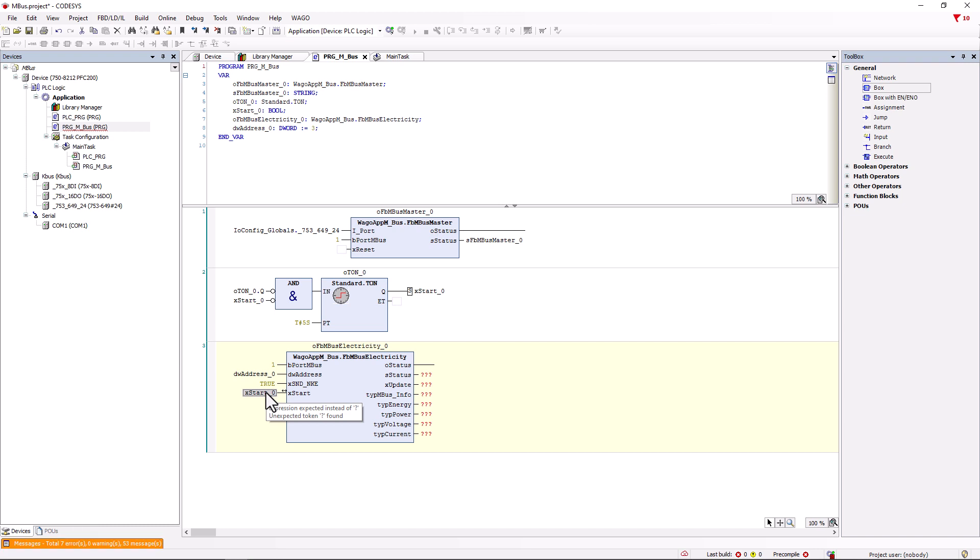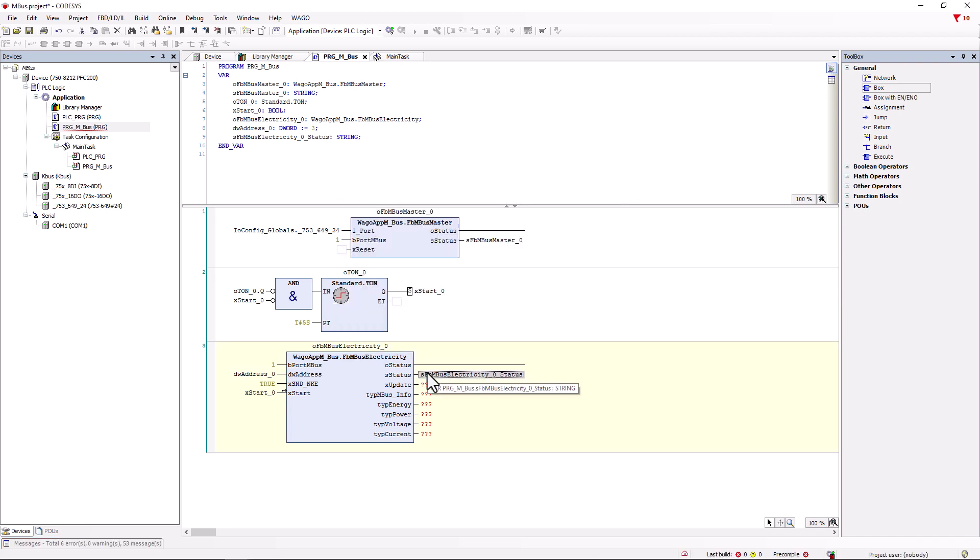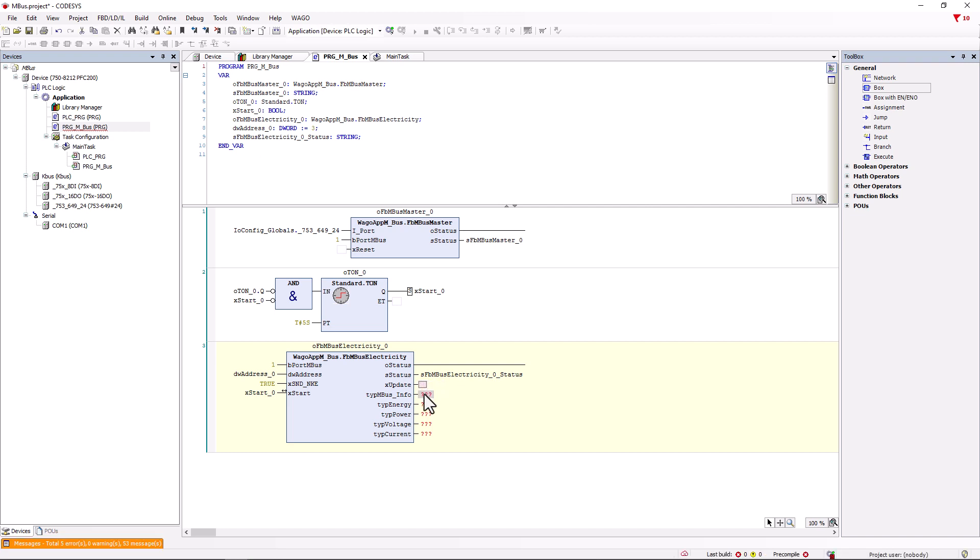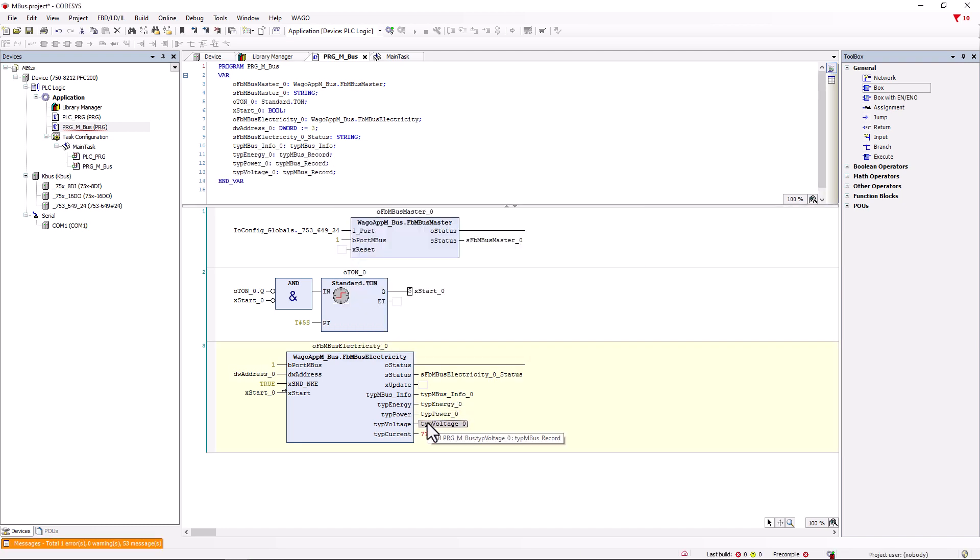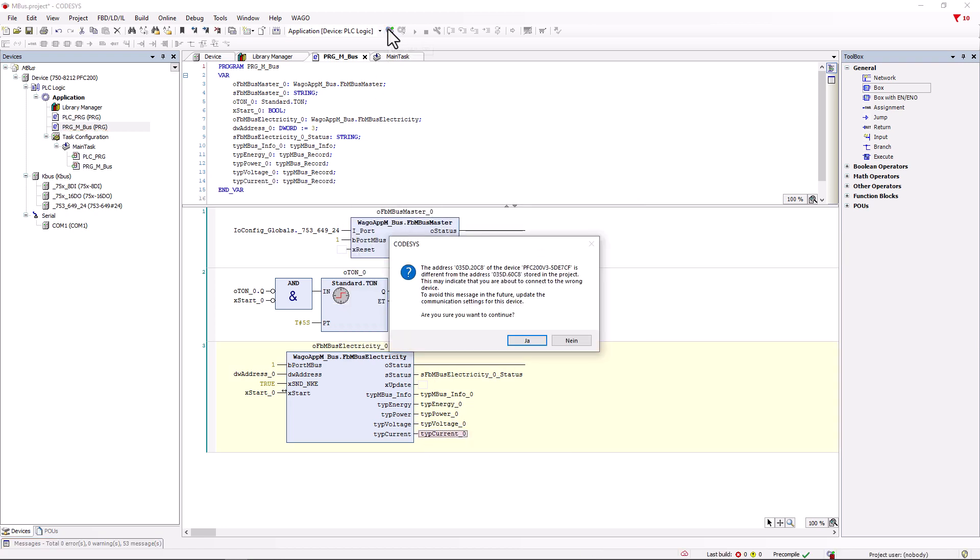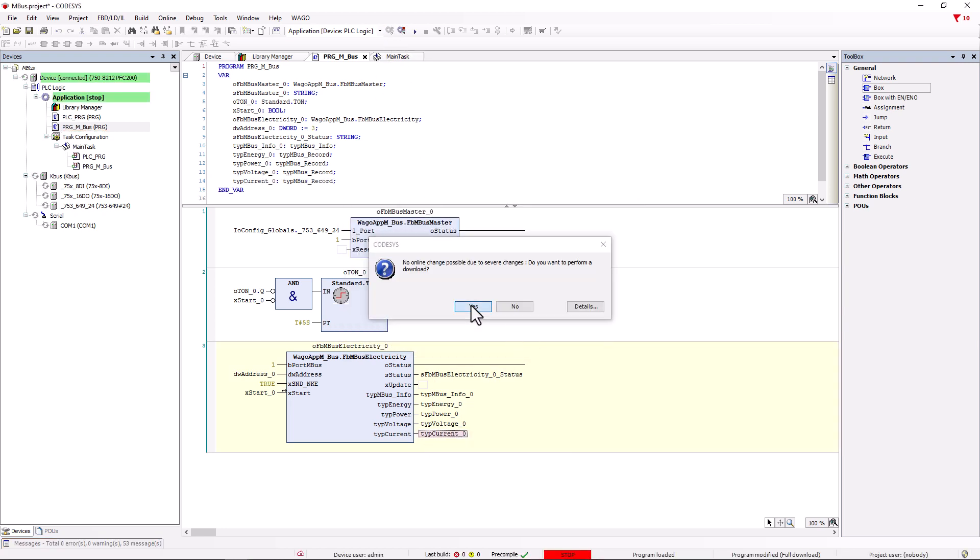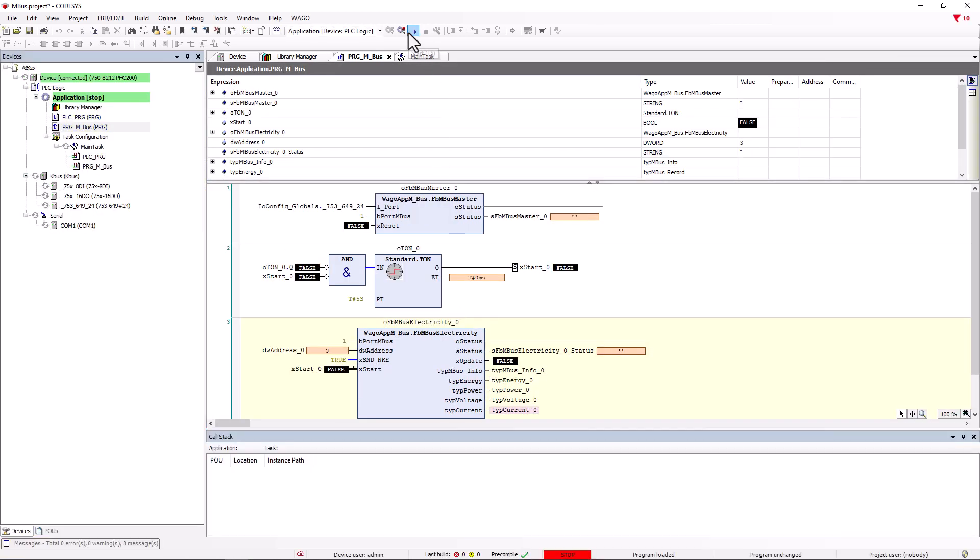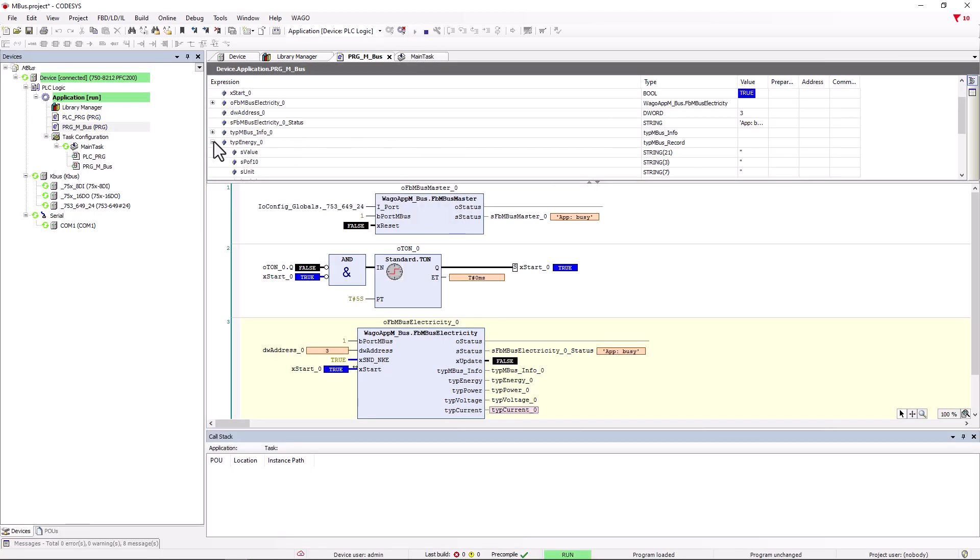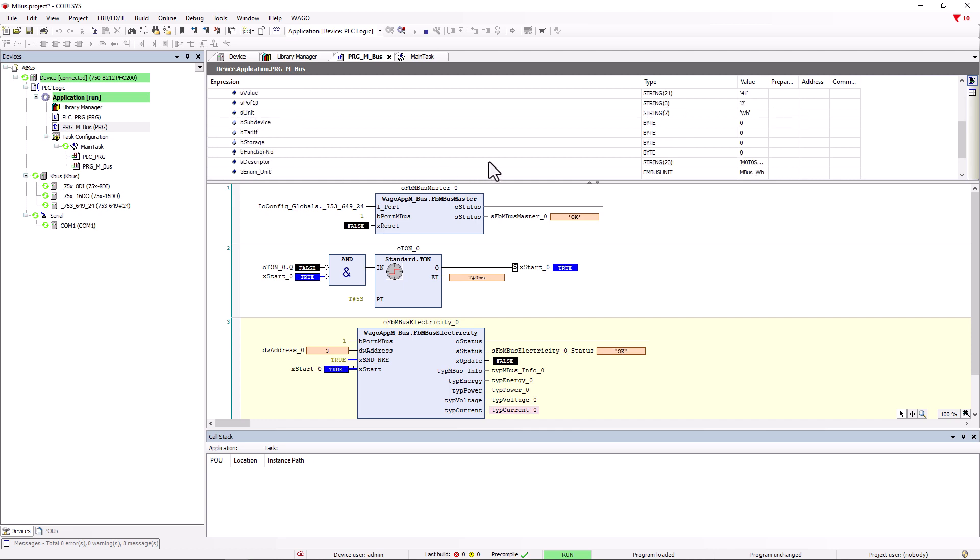When the query is completed, the electricity module resets xStart_0 to false and the TON module resets it to true after 5 seconds. Therefore, it flashes. The values of the meter are now made available at the outputs of the module and we assign unique variables to each output. We do not need the xUpdate output here. This value is true if a valid telegram was successfully received. This allows us to read out all values that the function block electricity provides. If we log in now and read out the values, we see that the values are still somewhat strange to represent and still have to be converted.